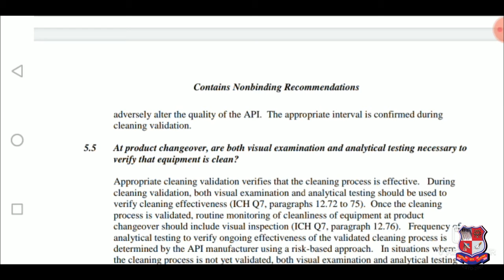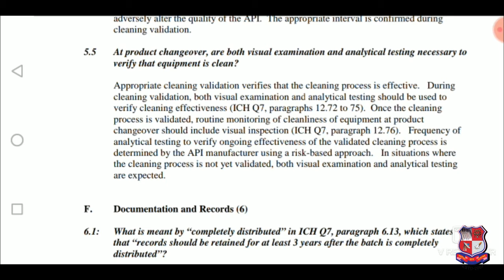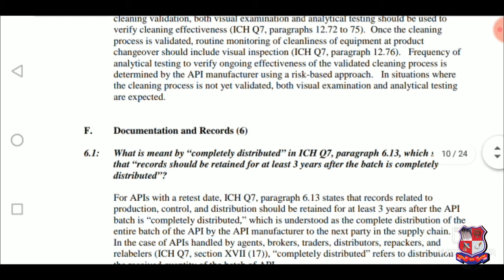At product changeover, are both visual examination and analytical testing necessary to verify that the equipment is clean? So the answer is, appropriate cleaning validation verifies that the cleaning process is effective. During cleaning validation, both visual examination and analytical testing should be used to verify cleaning effectiveness. Once the cleaning process is validated, routine monitoring of cleanliness of equipment at product changeover should include visual inspection. The frequency of analytical testing to verify ongoing effectiveness of the validated cleaning process is determined by the API manufacturer using a risk-based approach. In a situation where the cleaning process is not yet validated, both visual examination and analytical testing are expected.